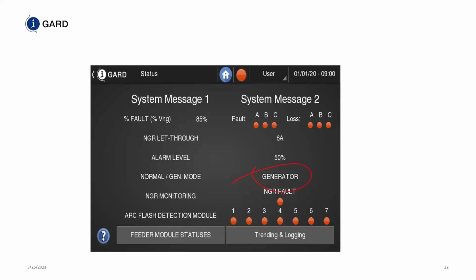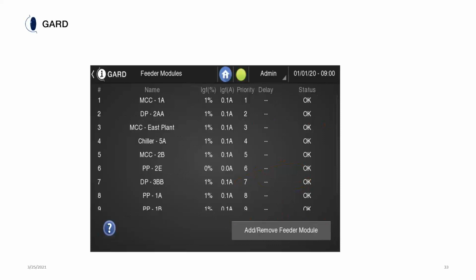So much so that some of our customers came up to us and said, I'm going to put this on a standby generator, but I don't want to hear the alarm go off, because the voltage on a standby generator is always off unless it's on. The predominant voltage on a standby generator is no voltage at all. So we put in a generator mode so that it doesn't alarm all the time if the generator is de-energized. So at a glance, you can tell what the fault current is and what the priority is on any phase or any feeder.